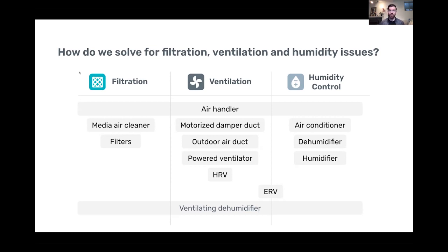For humidity control, I'm not sure how many people are in the world of heating and cooling, but air conditioners are dehumidifiers. They do a great job at pulling moisture out of the air when they're running. And the dehumidifier is an optimized version of an air conditioner for that purpose. It's a dedicated dehumidifier. Here we're talking about whole home solutions. So we're talking about a whole home air cleaner, a whole home dehumidifier, and a whole home humidifier. So something like a steam humidifier or a reheat dehumidifier. And these are various ways to control humidity. There's solutions like desiccant and a ventilating dehumidifier at the bottom here.